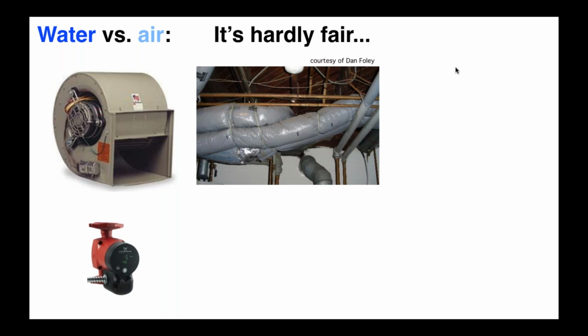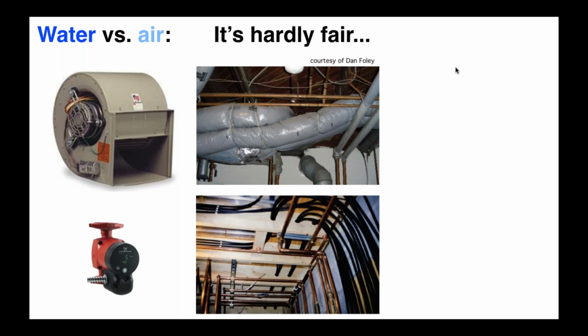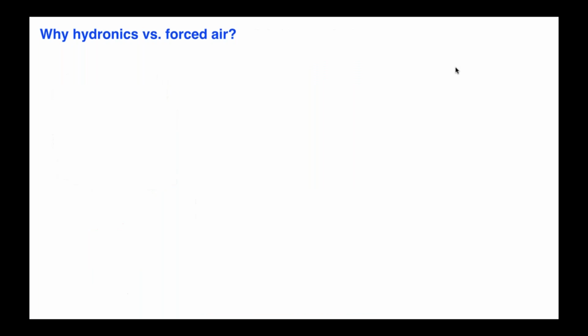If we go to water, we can use a much smaller and much lower power device, a circulator, a modern one with an ECM motor in it. And we can push that water through much smaller, what I'll refer to as conduits. You know, we call them pipes or tubes. You're looking there at 1/2-inch PEX aluminum PEX tubing that is being routed along floor joists, in some cases through the floor joists, much less invasive to the structure compared to a properly designed duct system.